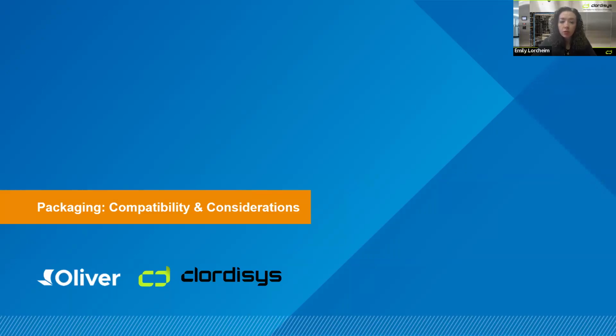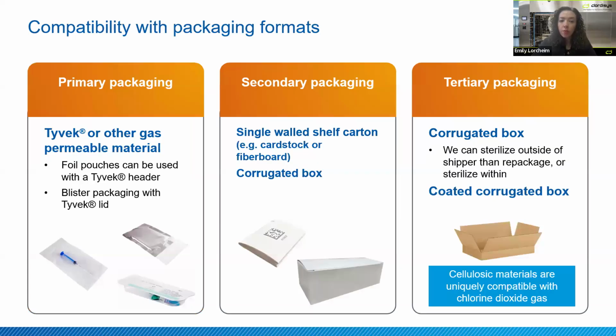Going into different packaging. So things you can think of in terms of compatibility and what types are compatible with the process. So for primary packaging, you want something that gas will be able to penetrate. This meaning not a sealed foil pouch. You can have foil as long as there's a Tyvek header, but typically you'll see Tyvek in film-based pouches or solely Tyvek. Now, in terms of secondary packaging, you can have single-walled shelf boxes, corrugate, single-walled fiberboard, and you can also have instructions for use.